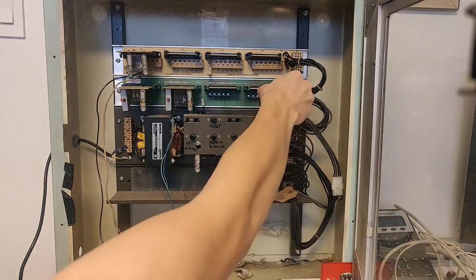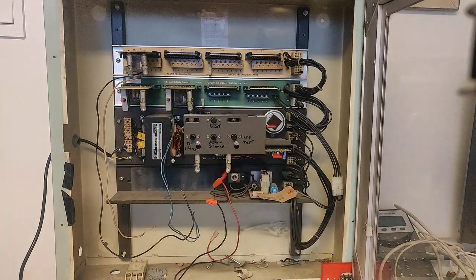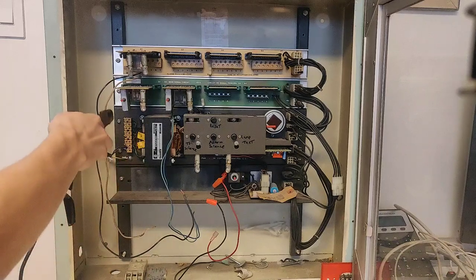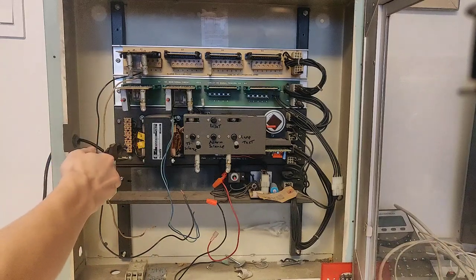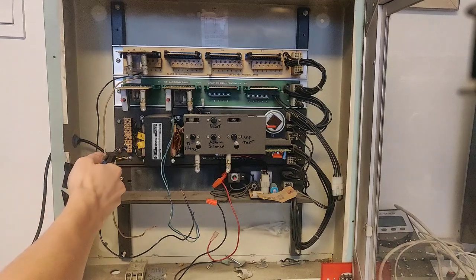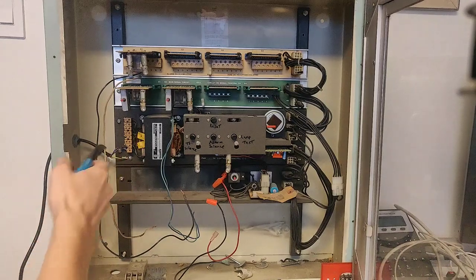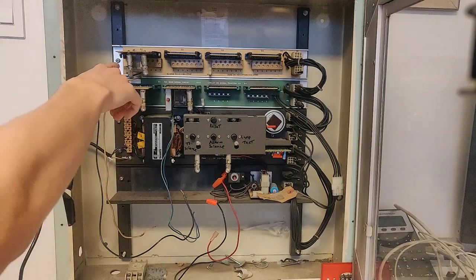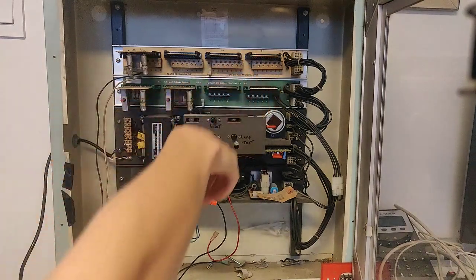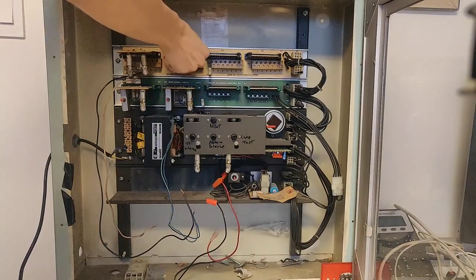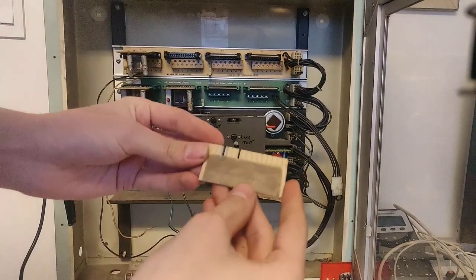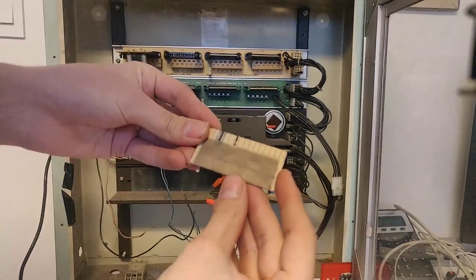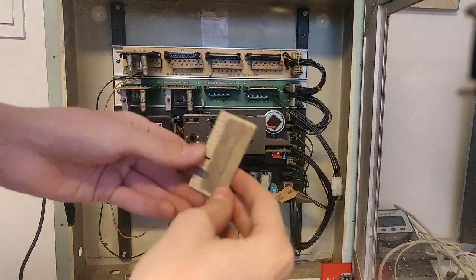This is the very annoying buzzer. This is your power inputs on this side as well as some connections for annunciators and accessories. And I believe there's a relay here but we'll go over that later. One thing worthy of note: if you have less than all four cards in each section, you will need this short card here. You can see it's just a simple circuit board with a little jumper. The fire alarm panel will not work correctly without these present.